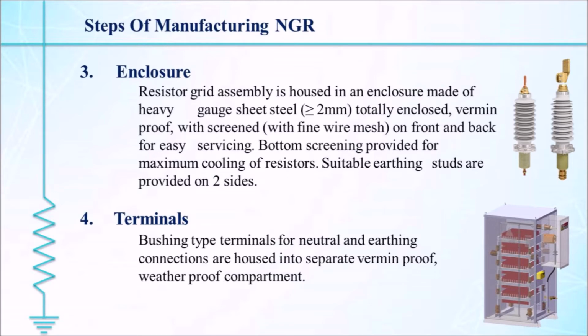Finally, this construction is installed in the panel, and here we use the insulator to avoid the contact between the NGR and the panel. At the end, the two terminals which we have brought out are taken out of the panel with the help of bushings, and that's how the manufacturing of an NGR is done.